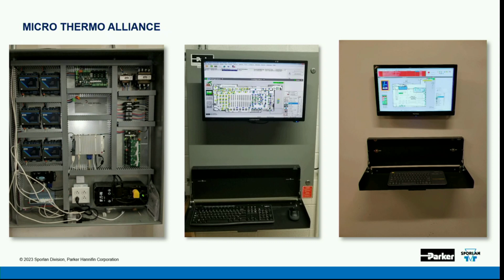So what we have built in Microthermo is called delayed install. For those of you who work on Microthermo, you might have used this already. What you do when you do delayed install is go to the icon, press the virtual install button, then go to the physical node and press the service pin button. You'll see a very fast handshake in the lower left-hand corner that, yep, you're on the right node and it sent the parameters, but it'll stop there.